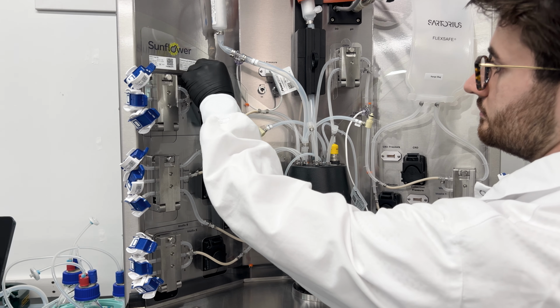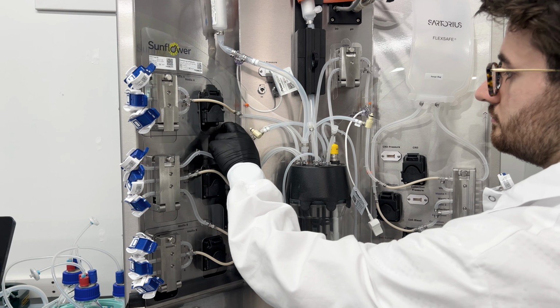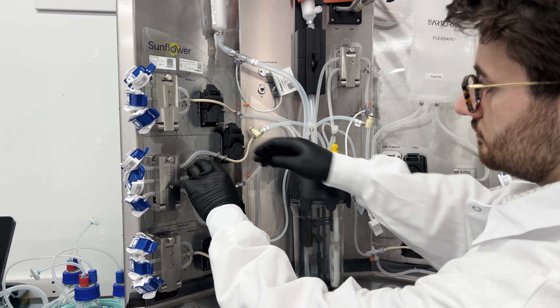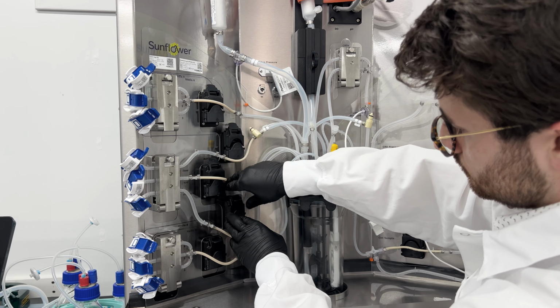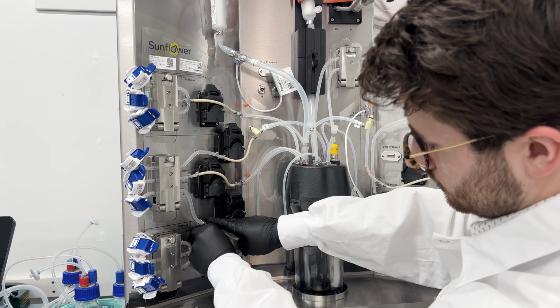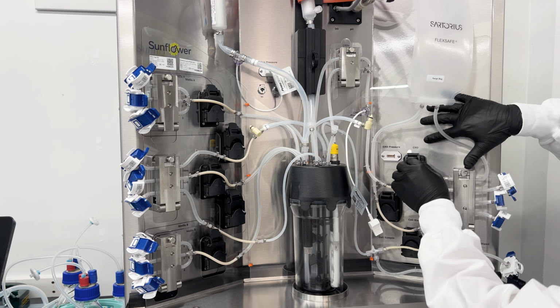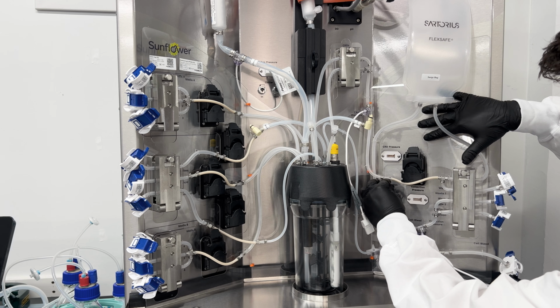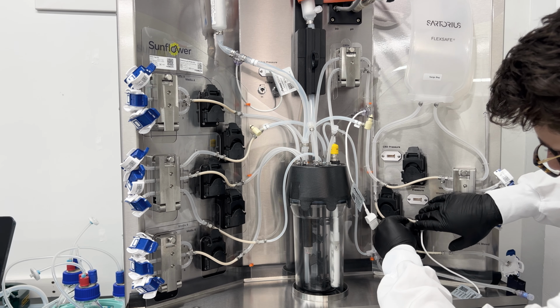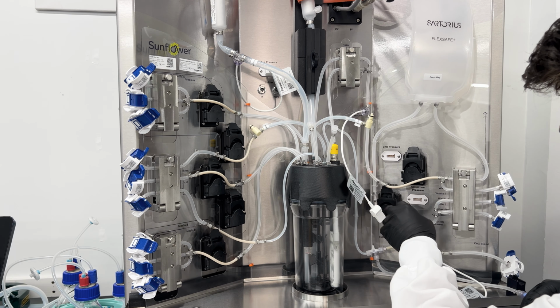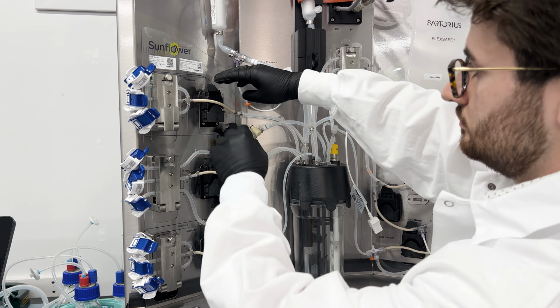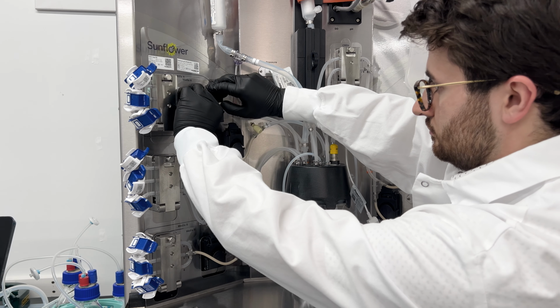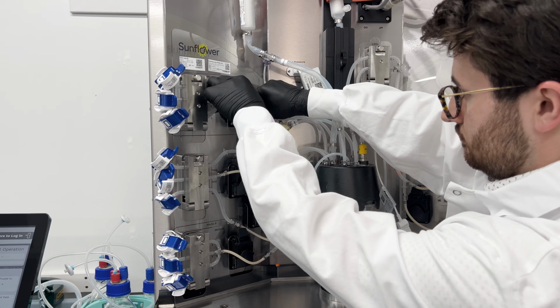Now, we will open all 8 pumps on the system so we can install the pump tubing. These pumps are responsible for delivering bioprocess fluids, like cultivation media or pH control fluids, into the bioreactor, and also for withdrawing spent cell culture fluids, or biomass, from the reactor to the collection vessel or waste container. The tubing is attached to the loom so that it is obvious which pump it should be installed in.